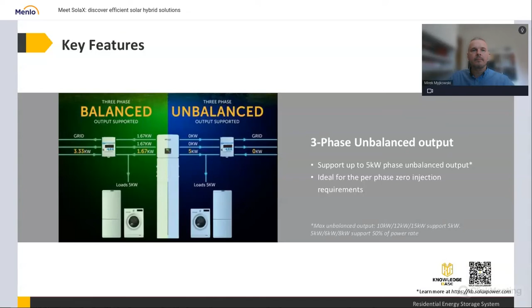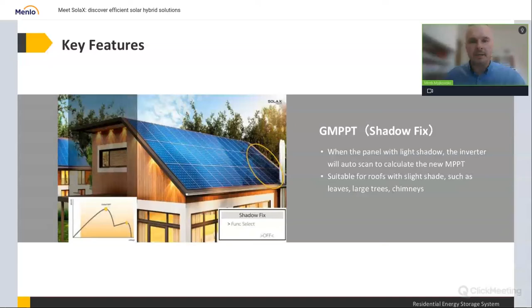Right, GMPPT, that is shadow fix, a scanning. So if you have situations like at some stages of the year, the sun is so low that the tree that doesn't bother in the summertime does bother at other times of the year. So it casts shadow on a few panels. GM shadow fix is just improving the work of the MPPT, like squeezing the string to take more power from those PV panels, even when they are a little bit under shade. That's what this function is for, in situations like chimneys and trees, maybe leaves or some kind of dirt lying on the PV panels.